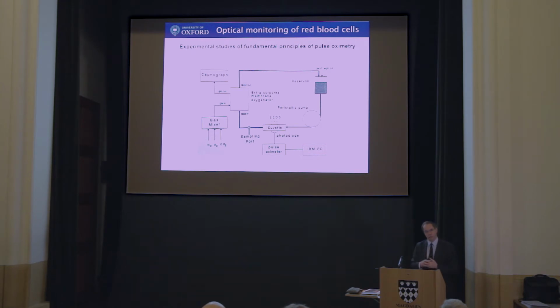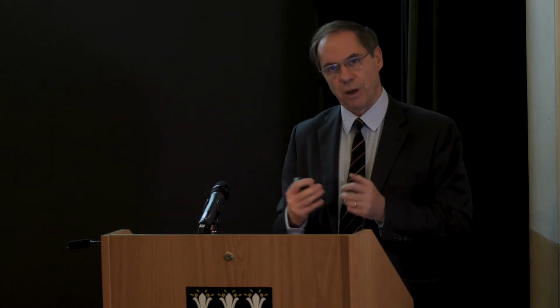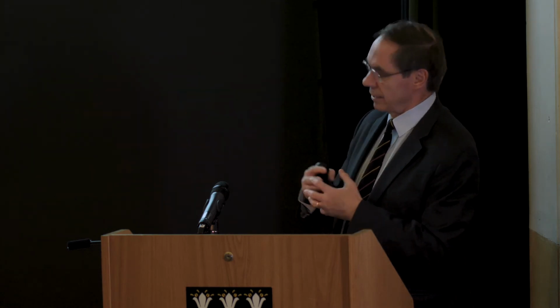In normal conditions, your oxygen saturations will be in the upper 90s because most of the Hb will actually be HbO2, and as the O2 is absorbed, you go down to venous oxygen saturation, which is only 75%. Because the Hb and the HbO2 molecules have different absorption spectra, with a 2 wavelength measurement you're able to work out their relative concentrations and hence the oxygen saturation.